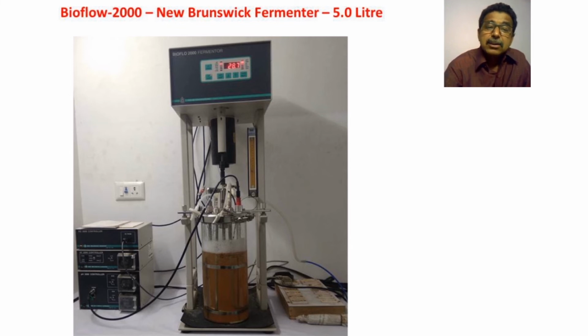Okay, and of course it is top driven. The control unit is on top, and the addition units are for the probes connecting and controlling. So additional units are here: one is the pH controller, one is the antifoam controller. For pH you need acid and alkali to be added, and that is why two peristaltic pumps are there for pH. For antifoam only one peristaltic pump is required.